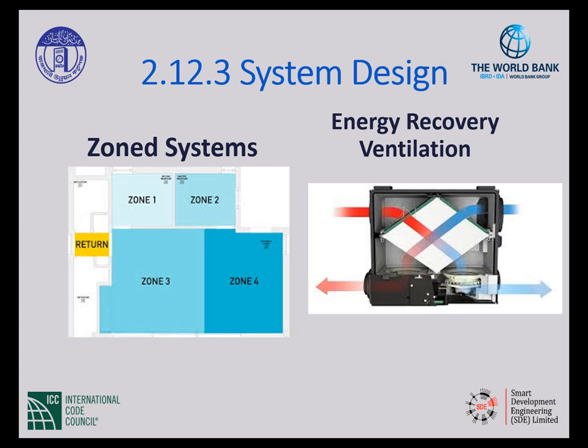Another thing it says on system design is that we're going to look at different ways of load variation. So consideration has to be given to changes in the building load and the system designed so that maximum operation efficiency is maintained under part load conditions. What is that saying? It's saying sometimes I'm not operating my building full bore, so my system has to be able to operate, and have controls to operate, in part load conditions. The total system shall be separated into smaller zones having similar load requirements so that each zone can be separately controlled to maintain optimum operating conditions by reducing waste of energy. So in this example here, we have this building that has different uses. So it's saying you break the building up into zones of like uses.